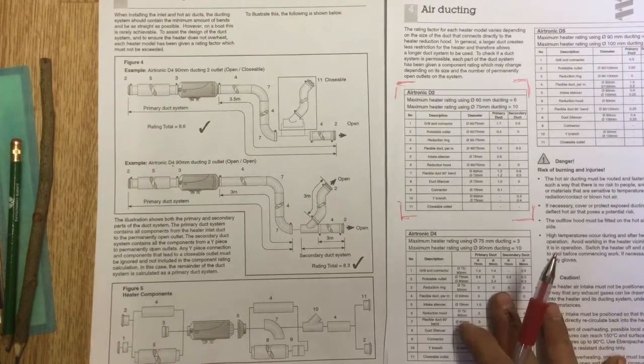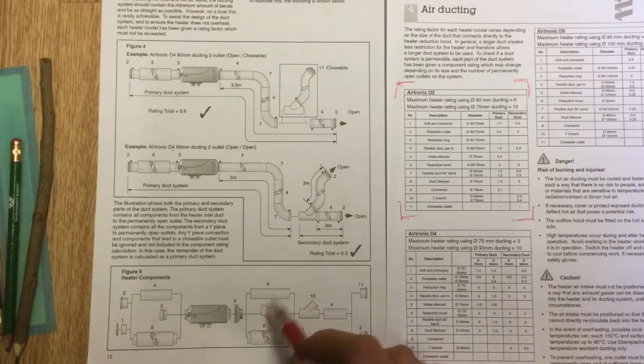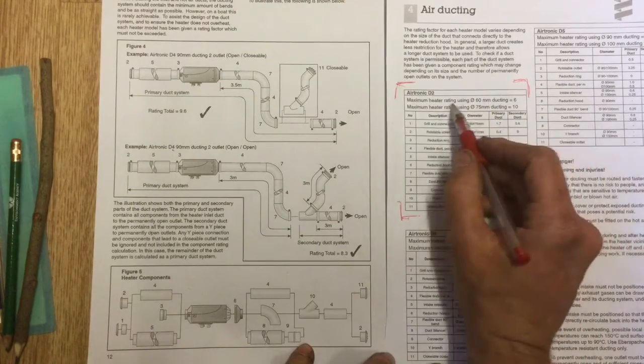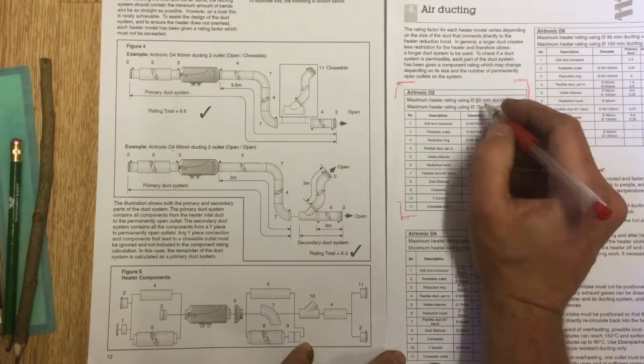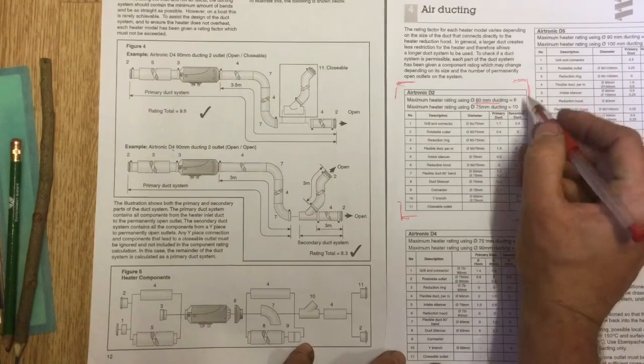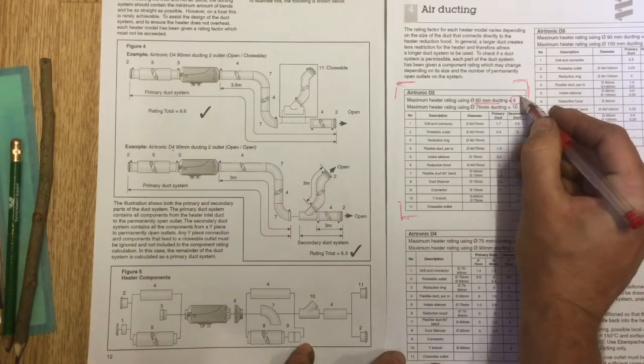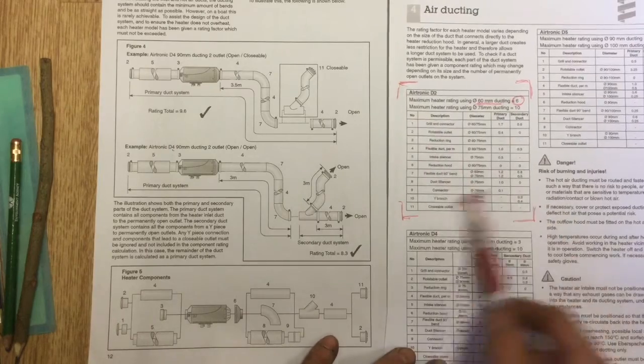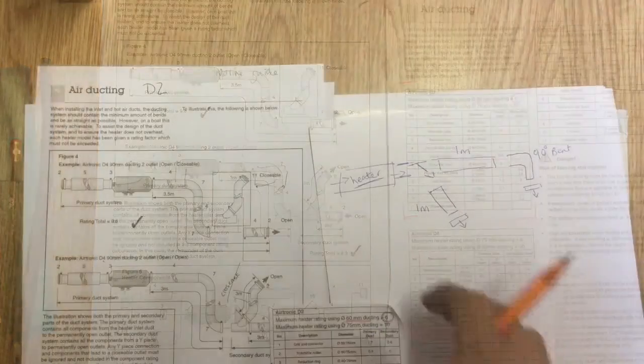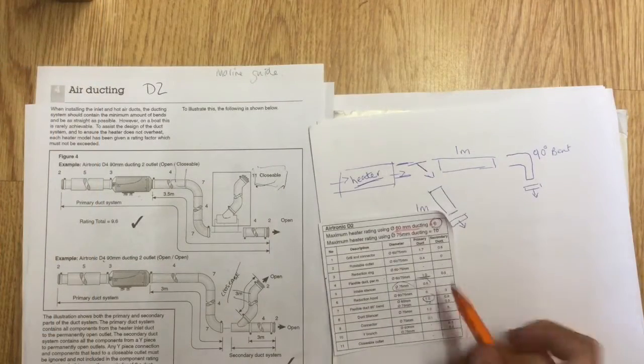We need to consider how big our ducting is first. If we have 60mm ducting, which I think is fairly standard - this is the size I tend to use - I can have a maximum value of six. That's not six meters, that's just using this information below, a value of six. Let's take a minute to look at an example.